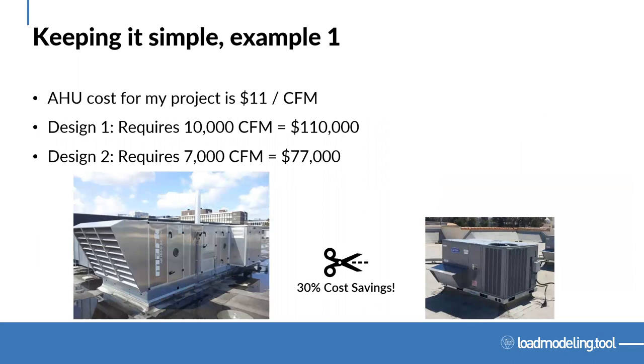A quick example: suppose the air handling for a project costs $11 per CFM all-in. If I have one design requiring 10,000 CFM based on my load model — internal loads, glazing, all of that — that's about $110,000. Now if I have an alternative design where I've reduced plug loads, gone with a slightly higher performing glass, and reduced the peak CFM needed to cool the space to 7,000 CFM, I get a 30% cost savings on that unit alone. So even before going to a detailed cost estimate, I can do these quick checks as I'm designing to see if I'm making a positive impact and optimizing that cost for the project.